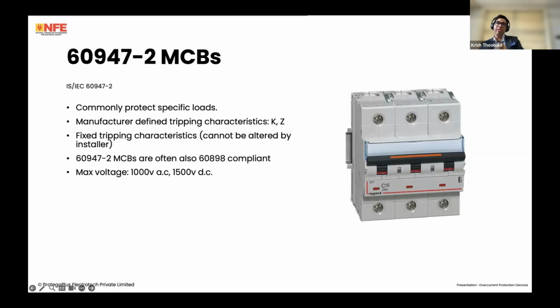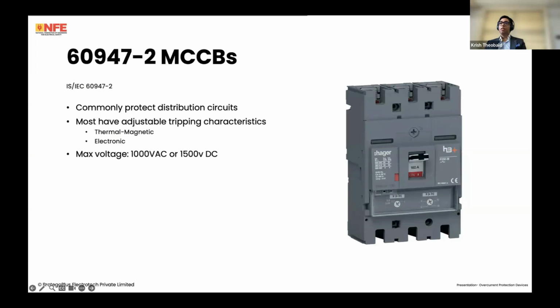Also, remember 60947 Part 2 is a very broad standard. It covers MCBs, MPCBs, which are motor protection circuit breakers, MCCBs, which are molded case. It also does RCDs, RCBOs, MRCDs, some protected devices for DOL starter, and DC solar photovoltaic breakers. So it's a very broad standard that we've got here. Then we come to the very familiar 60947 Part 2 MCCBs, especially if you're working in the industrial and heavy commercial sector. Again, we've got an IS standard, IS IEC 60947 Part 2.